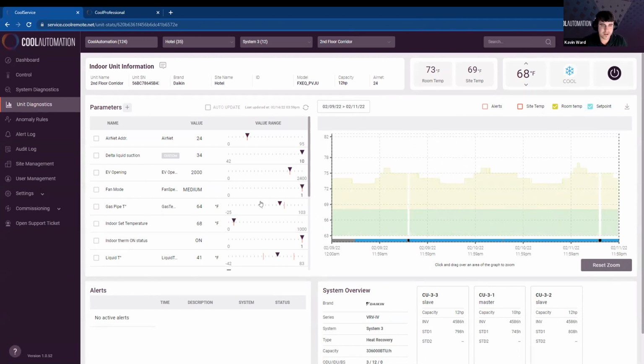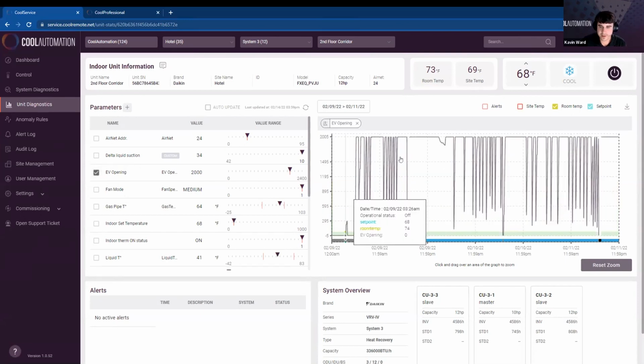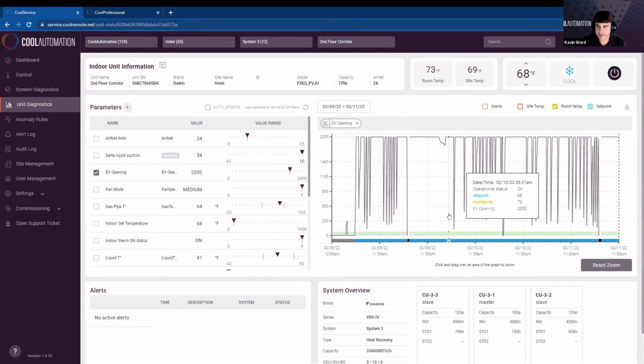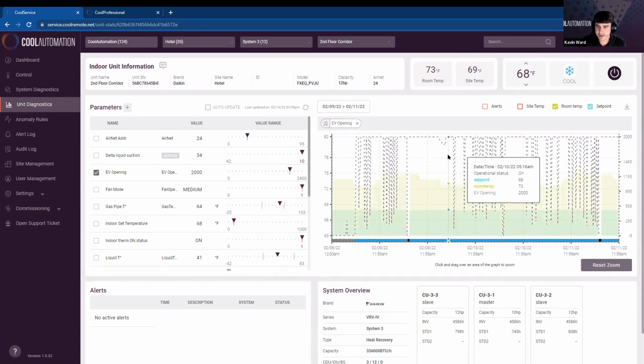And with an indoor unit, it is fairly simple. My main 3 parameters that I'd recommend checking are the valve opening for that indoor unit, the gas temperature leaving the coil, and the liquid temperature entering the coil. As we select these parameters and they move to our graph, we can see this valve position skews the way the data is presented. Luckily we have a dual axis system where we can move this scale to the right y-axis so that everything is presented a little bit more cleanly on the graph for you.